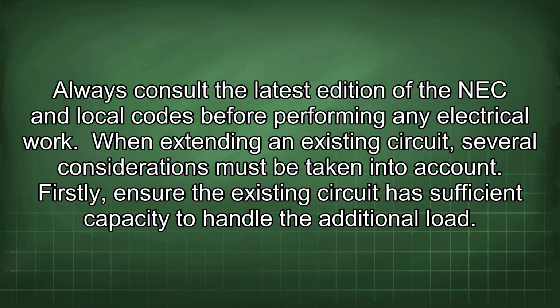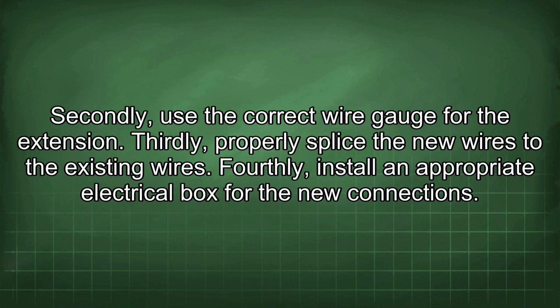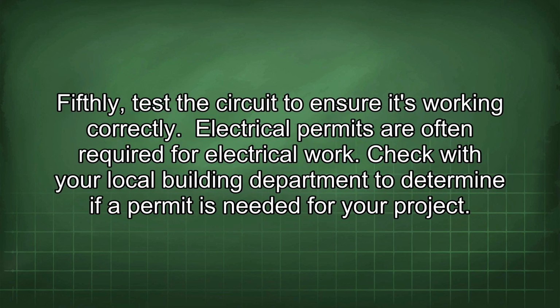While extending an existing circuit, several considerations must be taken into account. Firstly, ensure the existing circuit has sufficient capacity to handle the additional load. Secondly, use the correct wire gauge for the extension. Thirdly, properly splice the new wires to the existing wires. Fourthly, install an appropriate electrical box for the new connections. Fifthly, test the circuit to ensure it's working correctly.